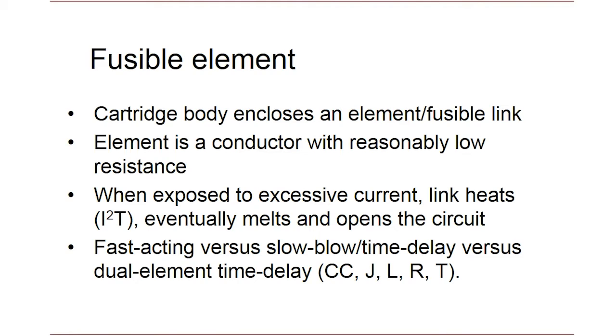Traditionally, single element fuses are a compromise — either designed for short circuit or overload protection characteristics. You can design that single element fuse to be very fast-acting, or sacrifice that speed and make it time-delay. This is a significant tradeoff, especially when protecting loads with very high inrush currents like motors and transformers. To address this, the fuse industry developed the dual element fuse — two separate elements connected together, one optimized for low magnitude overcurrent and the other for high magnitude fault conditions. Dual element fuses are found in classes CC, J, L, R, and T, and represent the vast majority of fuses in the low voltage power distribution market.